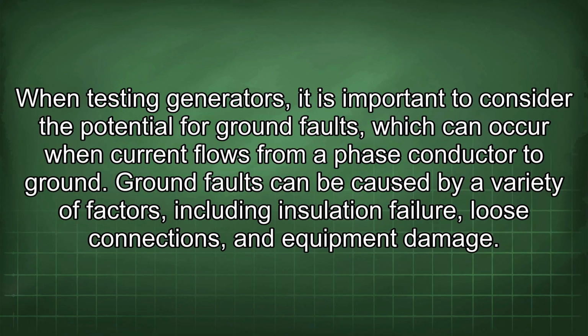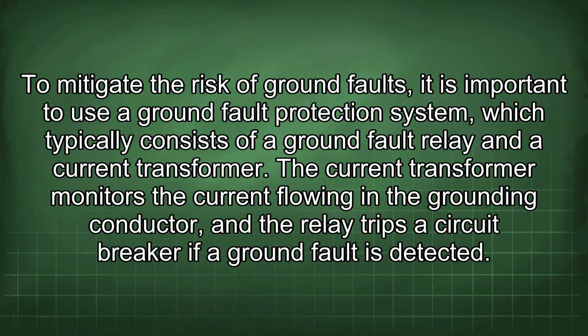When testing generators, it is important to consider the potential for ground faults, which can occur when current flows from a phase conductor to ground. Ground faults can be caused by a variety of factors, including insulation failure, loose connections, and equipment damage. To mitigate the risk of ground faults, it is important to use a ground fault protection system, which typically consists of a ground fault relay and a current transformer. The current transformer monitors the current flowing in the grounding conductor, and the relay trips a circuit breaker if a ground fault is detected.